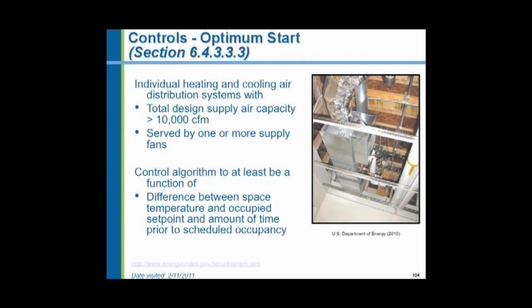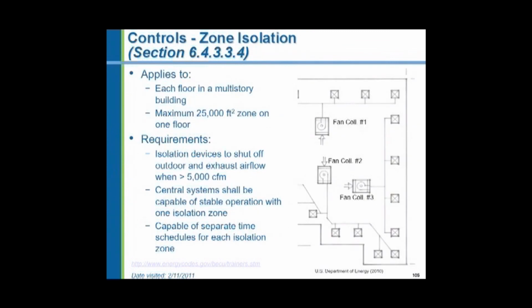Optimum start controls, as I mentioned before, the system learns the performance of the building. It takes into account how long it takes the building to heat up or cool down. Isolate the zones one from another, have temperature controls and systems for each of them. The optimum design is to have individual temperature controls for each person in a building. Each person at his workstation or office would ideally have an individual temperature control. It may not be possible economically to do that. It may cost too much.